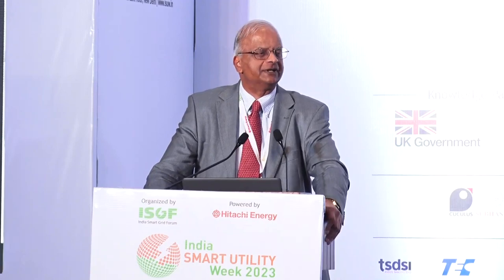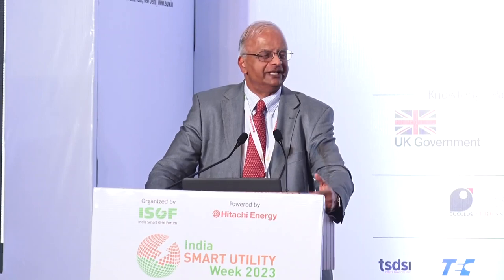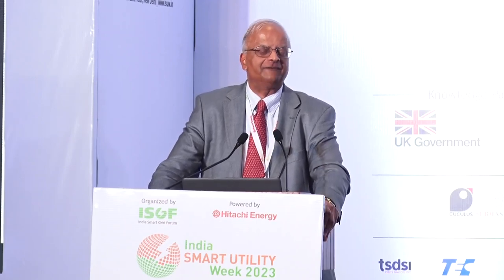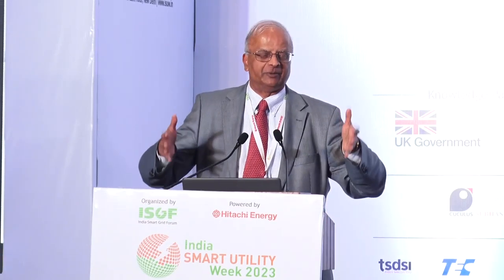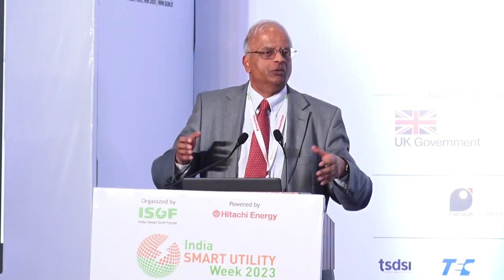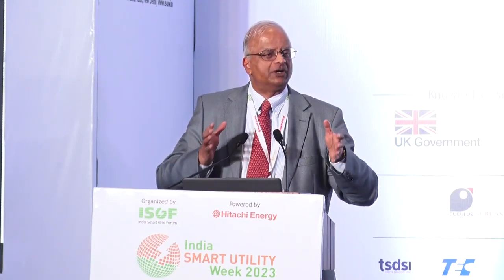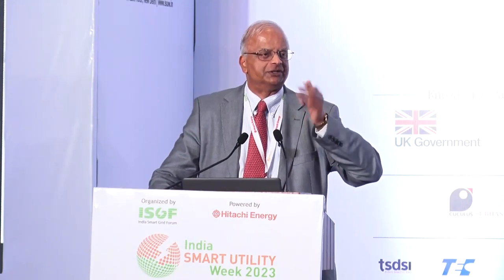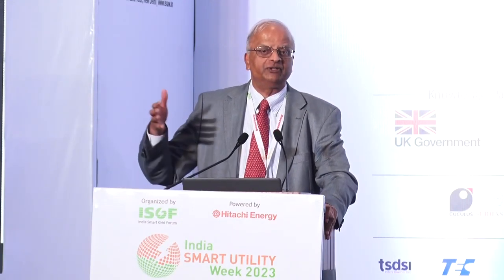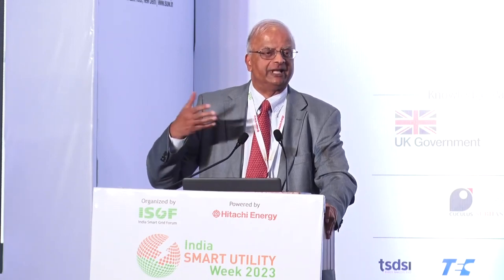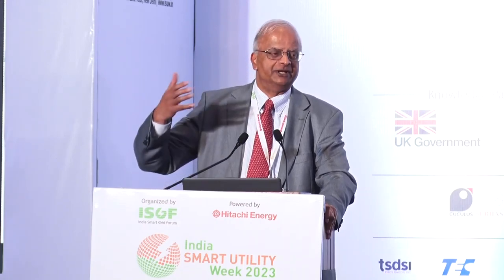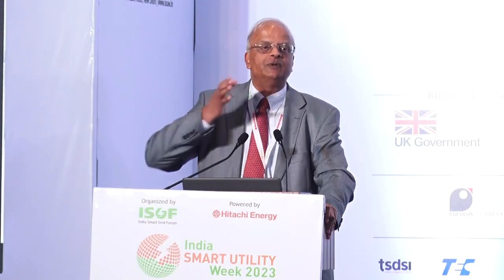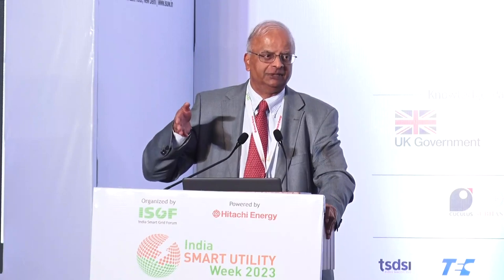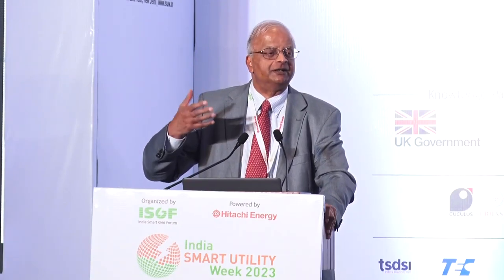So the question is how do we manage it dynamically? I have to look at three pieces. I have an electrical piece of equipment, say a transformer or cable, which we know we have loaded, and therefore what is the current operating temperature at T equals zero. I know the predicted load it should handle for the next hour. So I should be able to put it in my digital twin or through some formula to see if it can take it, and what will be the temperature at T plus one. Will it add 5 degrees, 6, 10, whatever?